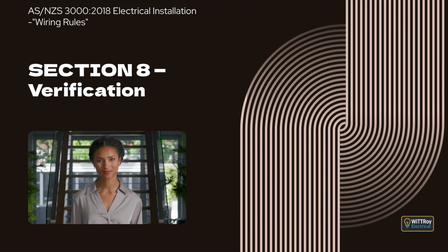The clause also reminds us that safety precautions must be taken during inspection and testing to protect people, property, and electrical equipment. Where work involves an alteration or repair to an existing installation, verification is required to confirm that the work complies with this standard and does not reduce the safety of the existing installation. The notes explain that extra inspection and testing may be needed for certain types of installations, and that in New Zealand, special attention is required for wiring and fittings located near conductive thermal insulation, as covered by NZECP 55.